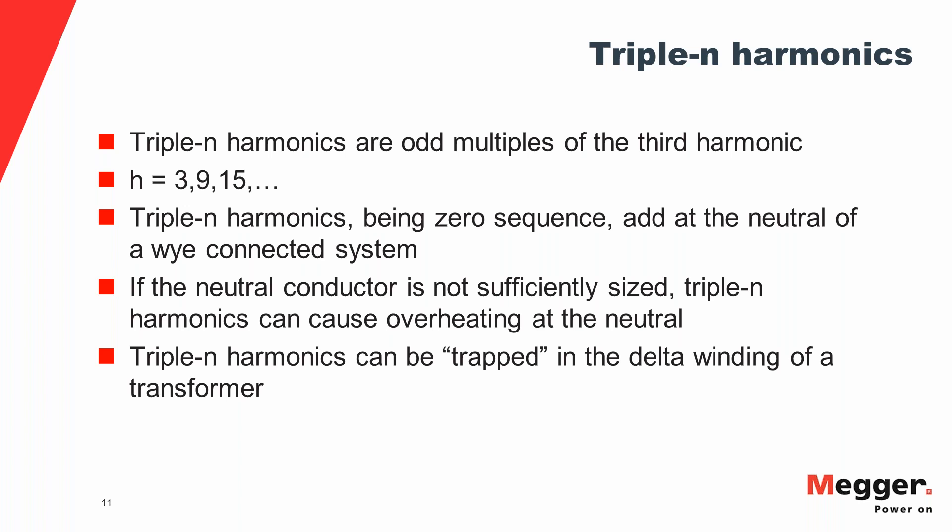The neutral is grounded. So if there is a lot of zero-sequence harmonics in the system, all of that will flow through the neutral, and if the neutral is not sufficiently sized, there will be overheating of the neutral conductor. Additionally, zero-sequence or triple N harmonics can be trapped in the delta winding of a transformer. One main function of the delta winding is to provide a circulating path for zero-sequence currents. On a grounded Y-delta system, zero-sequence currents flow into the Y winding and down to the neutral, but on the delta side they circulate within the delta winding and do not propagate further through the system.